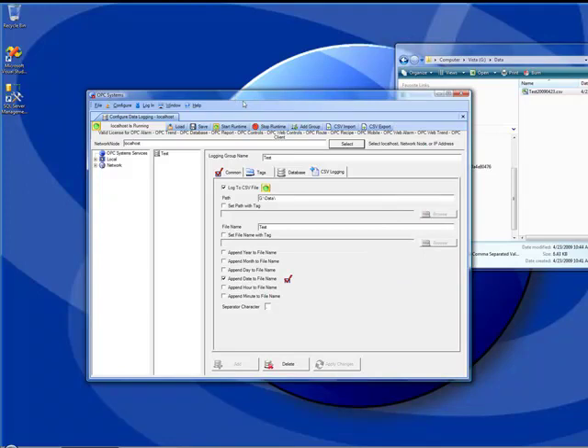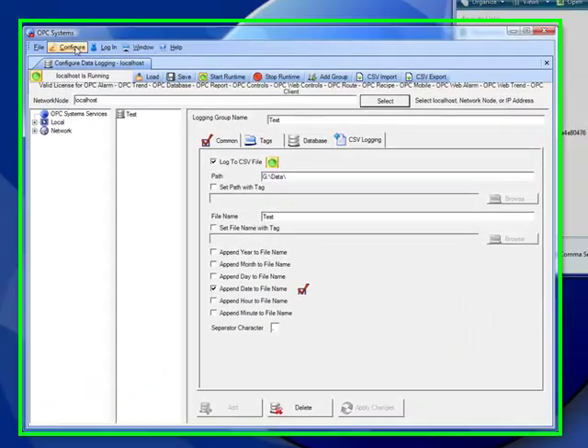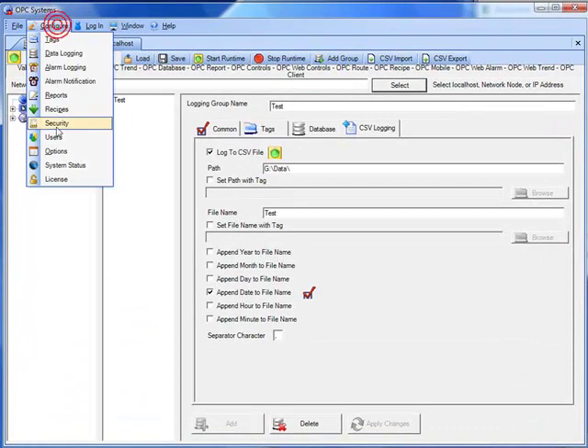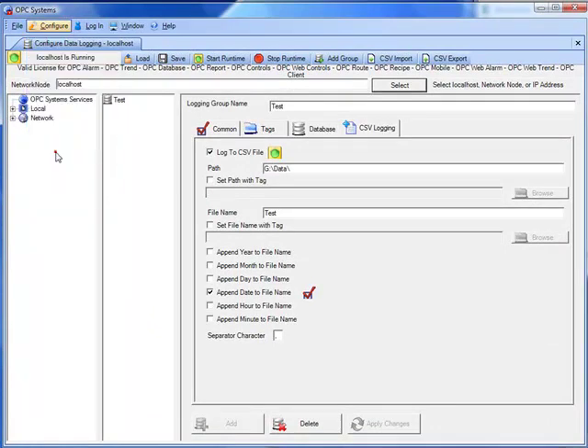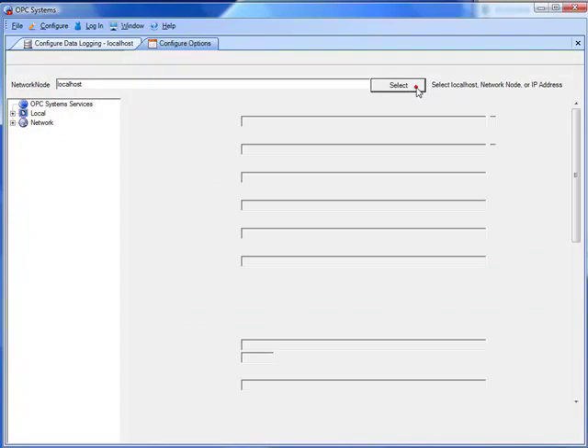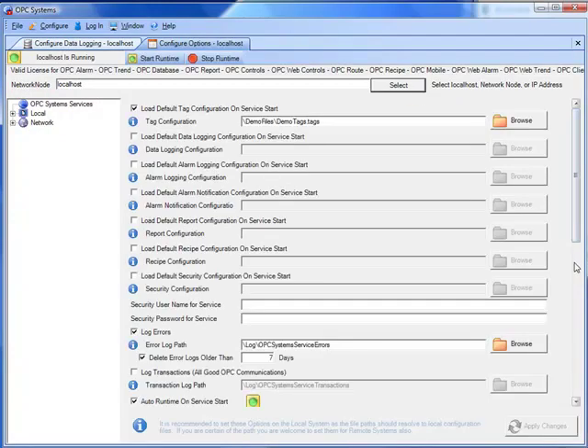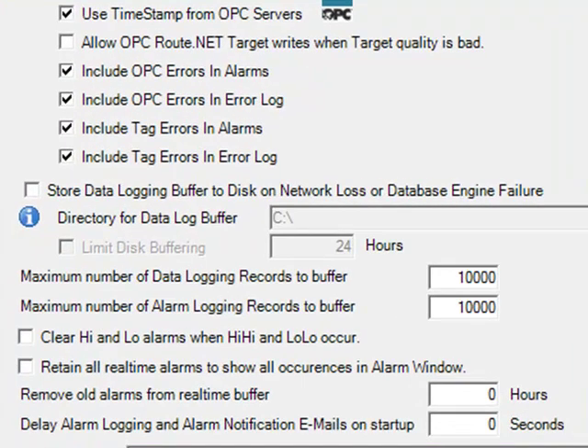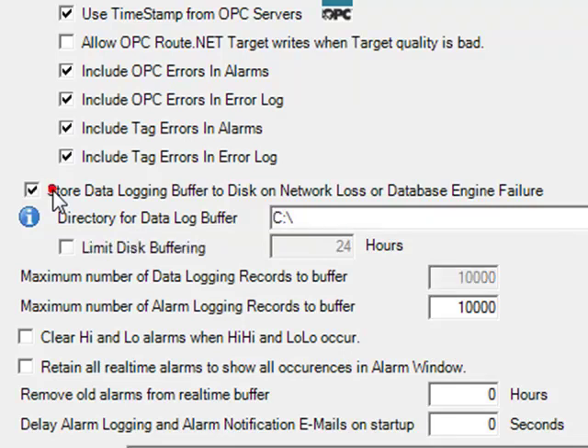We can also enable the feature under configure options to buffer data to disk. If we select configure options and select the local service, there is a feature called store data logging buffer to disk on network loss or database engine failure. So both on the data source and the system that is doing the data logging that may be the same system if you're logging from local tags, you would want to enable this feature for long-term data buffering. This way, you're only limited by hard disk space size when the data buffering is occurring. You can specify a drive and directory of where the temporary files will be stored when the data buffering is occurred.